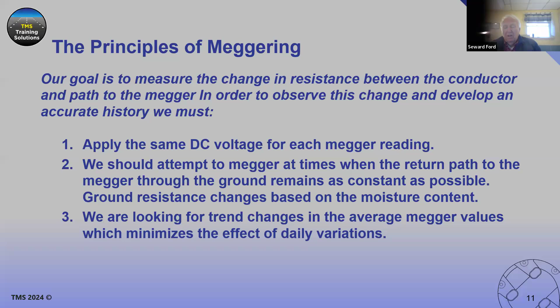That's the question I asked just a few minutes ago. What is the most appropriate DC voltage for Meggering an airport lighting series circuit? I'm going to get some input on this from maybe Keith or Carl or anybody, but is the voltage rating of the cable the key, or the normal operating voltage of the circuit? My position would be that after the circuit's installed and operating, then we would typically do a Megger reading using a voltage of probably 1,000 volts.